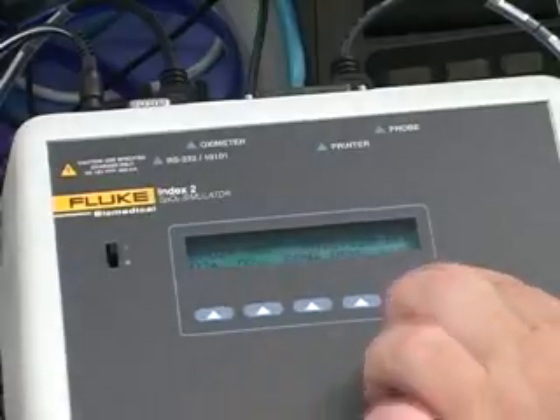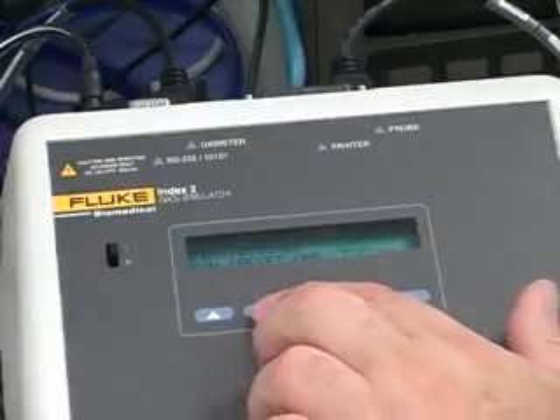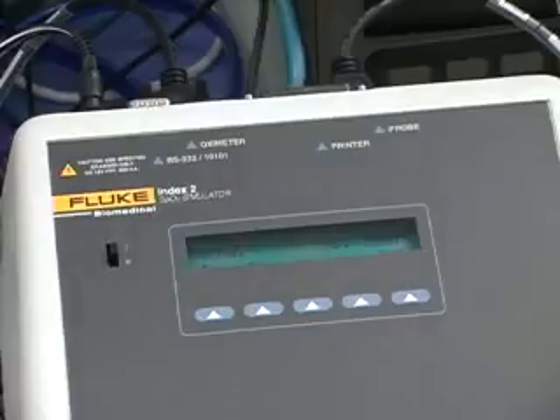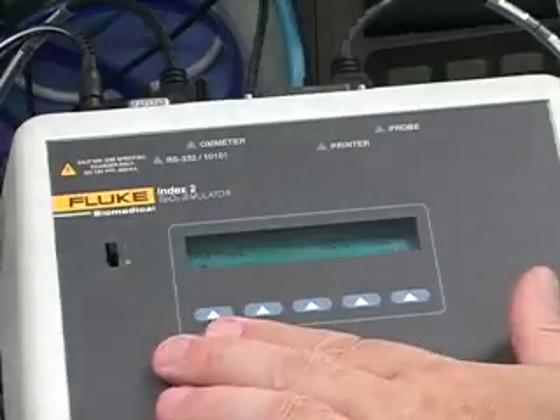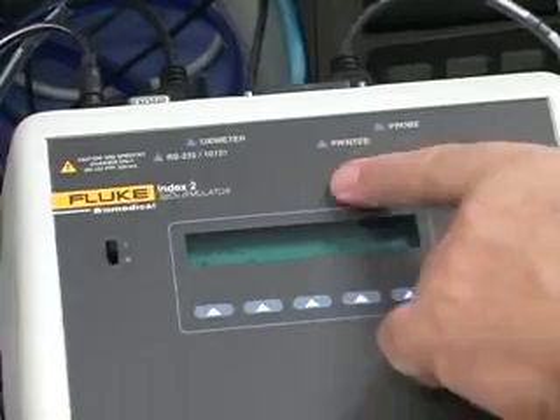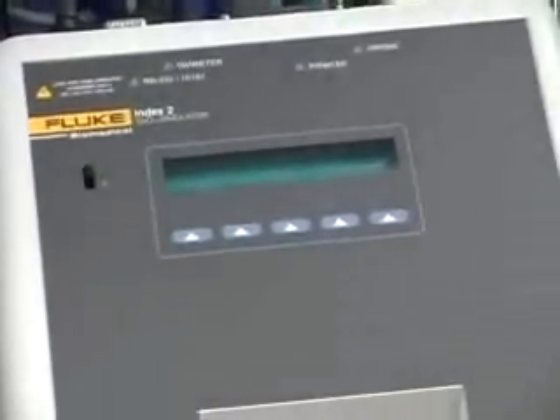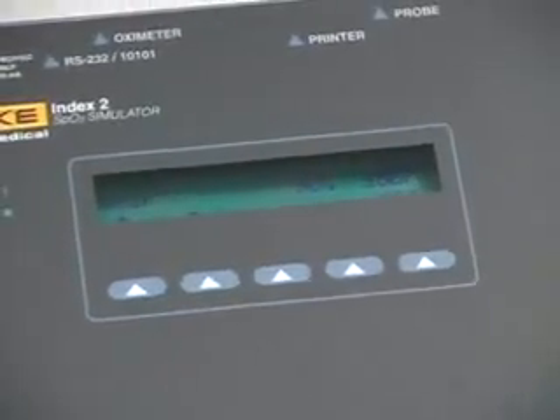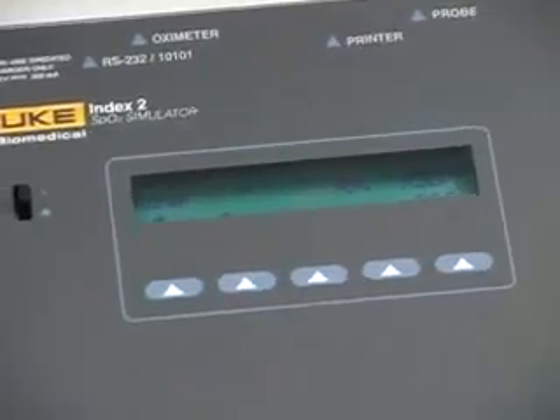Okay, in addition to that, we also do have capability of some preset selections, and with this we do have different pulse strengths, different heart rates, and different saturation levels. So it just defines the range of possible patients that you would have in the field. So a normal patient, but with a bit of a lower heart rate, but good saturation. And then this is a weak pulse, so you're looking probably at about a 50% pulse strength, and also a lower saturation and a little higher heart rate. So with this, then, we are looking at simulating more worst-case conditions.